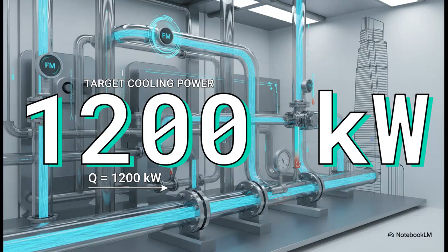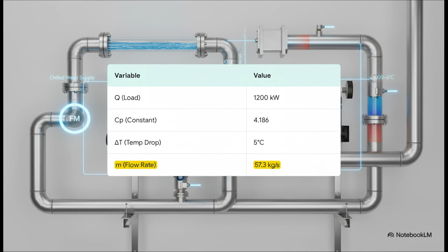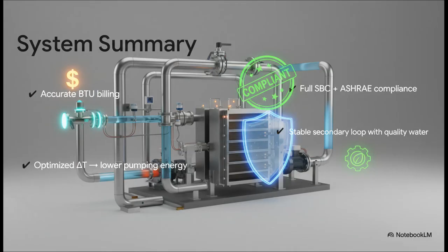So we take our values and we plug them right into that core formula. We know our target Q is 1,200 kilowatts, and we're designing for a 5 degrees Celsius temperature drop. With a little bit of algebra, the equation spits out our answer: we need to supply 57.3 kilograms of chilled water every single second. That's what it takes to meet the building's cooling demand.